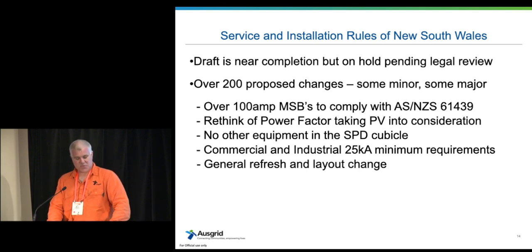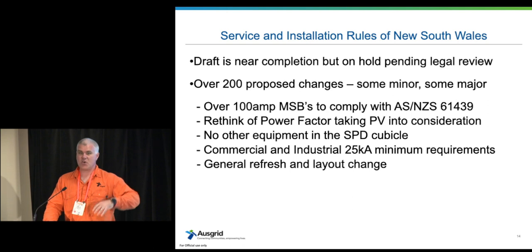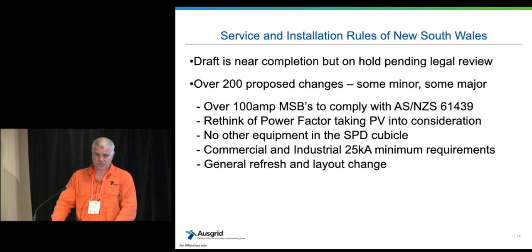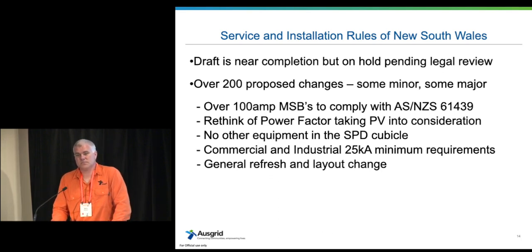And also looking at the commercial industrial 25 kA minimum. It's more just reinforcing that particular space there, because as you know, the network's continually evolving, and the kA ratings can significantly change as soon as we throw a substation in just around the corner here, because someone's decided to build another block of units or whatever and put a new sub in next door. So now all of a sudden that kA rating can blow out pretty quickly after the switchboard's already been installed. On that kA rating, you guys are trying to push that from the PLA to the switchboard? Yeah, correct.